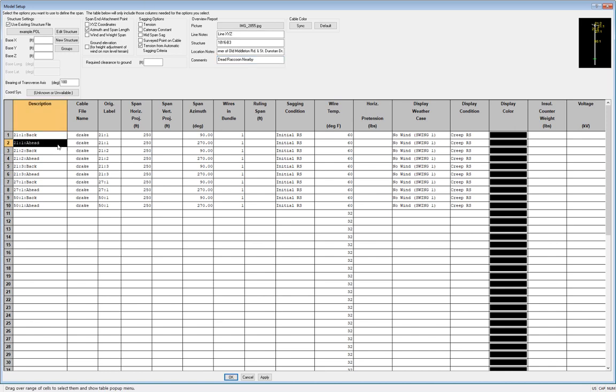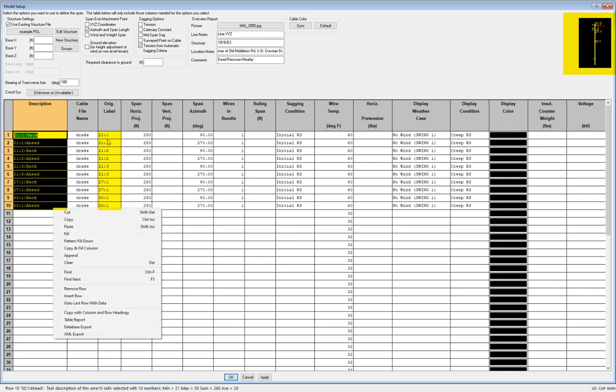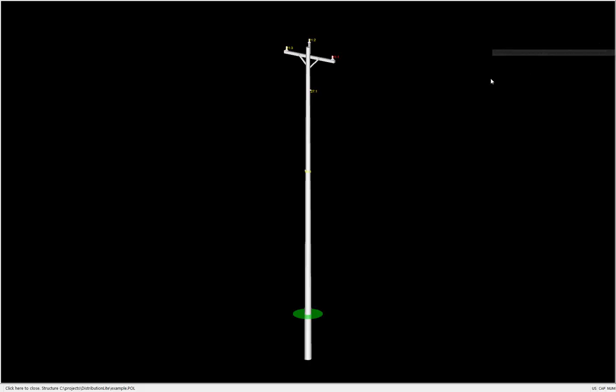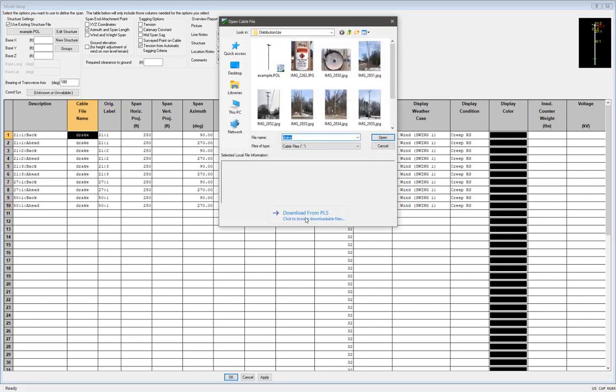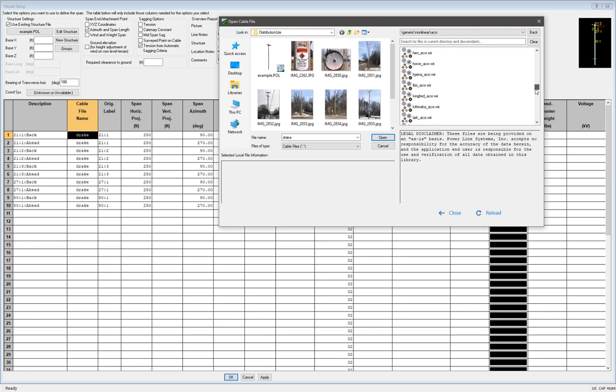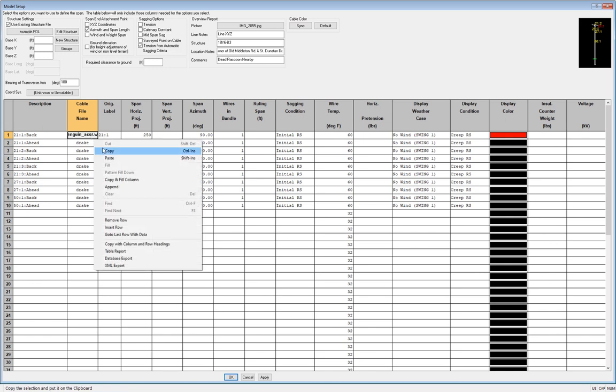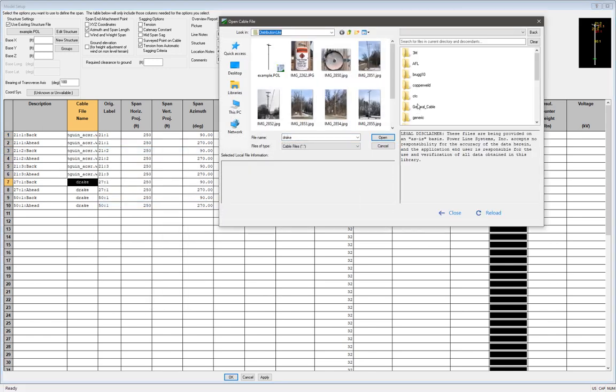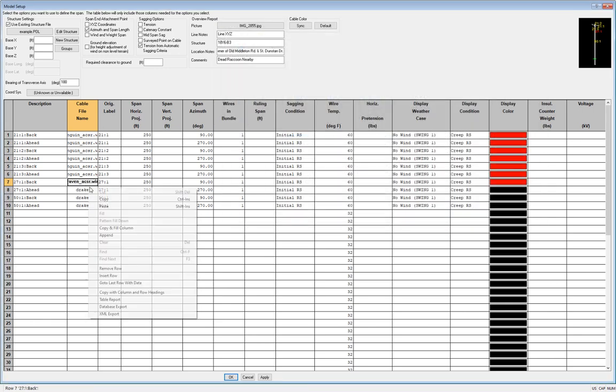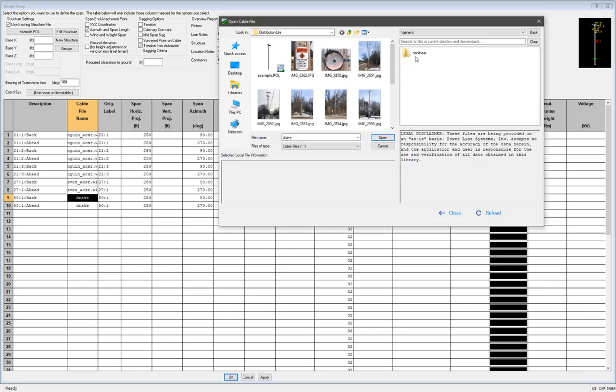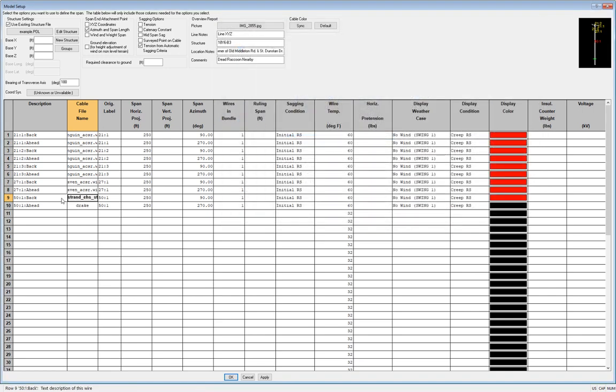In the table portion below, I can enter the wire and span information. I can look at these columns for the insulator groups and phase number and correlate them to the preview in the upper right corner, which I can enlarge by clicking on it. The wires I'll need to make some changes to. For insulator group 21, my primary three phase wires, this was going to be the 4-aught ACSR Penguin, so I'll navigate out to the website and download that cable file by clicking on this button. The neutral set number 27, we said was going to be 1-aught ACSR Raven, and I'll navigate to that. The communication wire, we said was going to be 1/4 inch EHS steel, but we'll need to modify that slightly for the communication cable that's lashed to the 1/4 inch messenger. But we'll start by just downloading the 1/4 inch EHS steel wire.